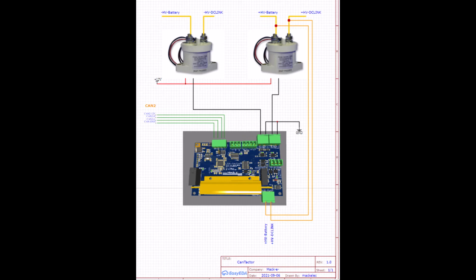So upon CAN instruction, it will initiate pre-charge, and if it fails to charge the DC link, or power to the inverter, it will send a fail message and shut down the negative contactor. If the pre-charge is successful, the positive contactor is energized.